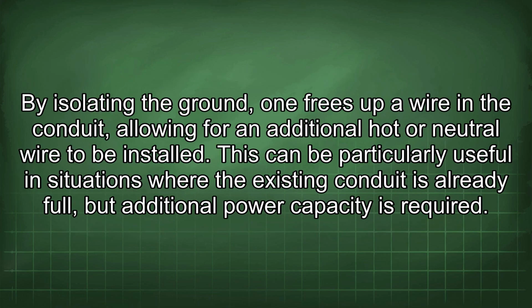By isolating the ground, one frees up a wire in the conduit, allowing for an additional hot or neutral wire to be installed. This can be particularly useful in situations where the existing conduit is already full, but additional power capacity is required.